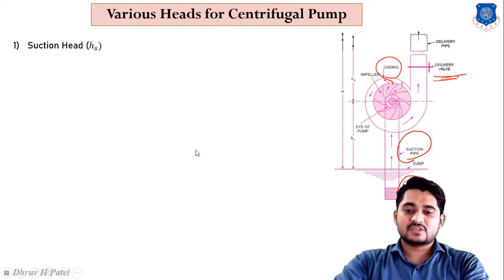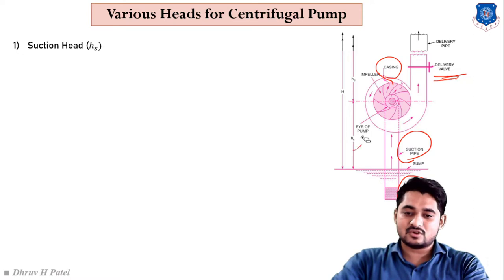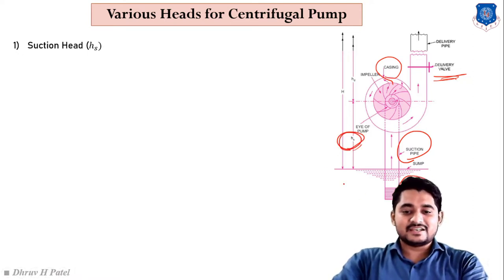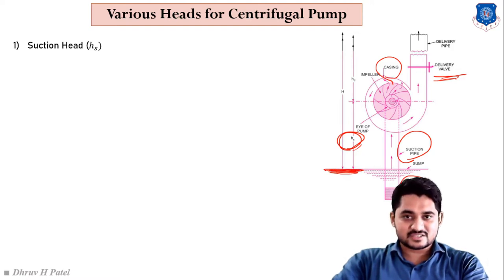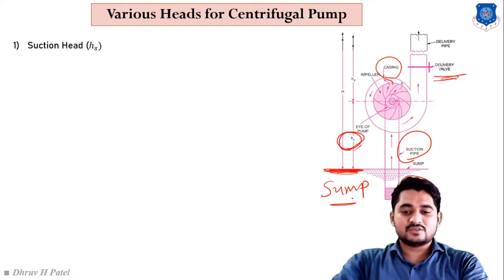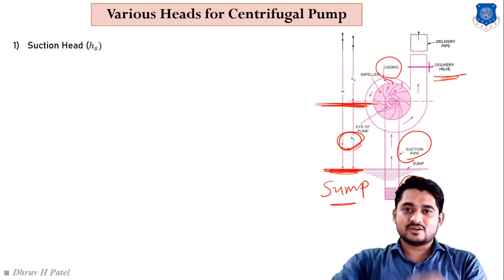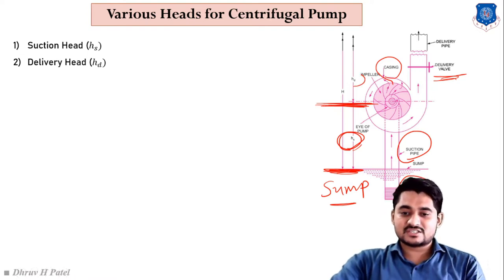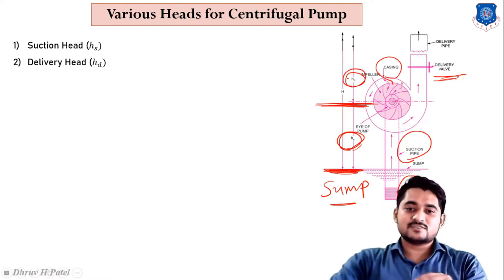The first head is suction head, represented by small h_s. It is the vertical distance between the suction level (sump) and the center of the shaft. The second one is delivery head h_d, which is basically the vertical distance between the center of the shaft and the upper level of the pipe, that is our destination.